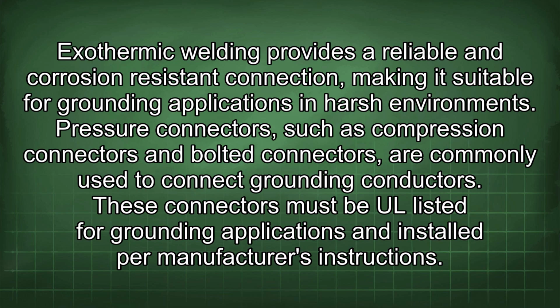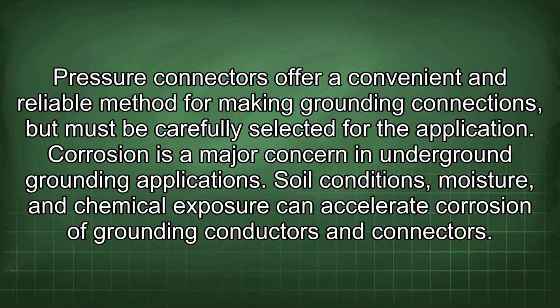Pressure connectors, such as compression connectors and bolted connectors, are commonly used to connect grounding conductors. These connectors must be UL listed for grounding applications and installed per manufacturer's instructions. Pressure connectors offer a convenient and reliable method for making grounding connections, but must be carefully selected for the application.